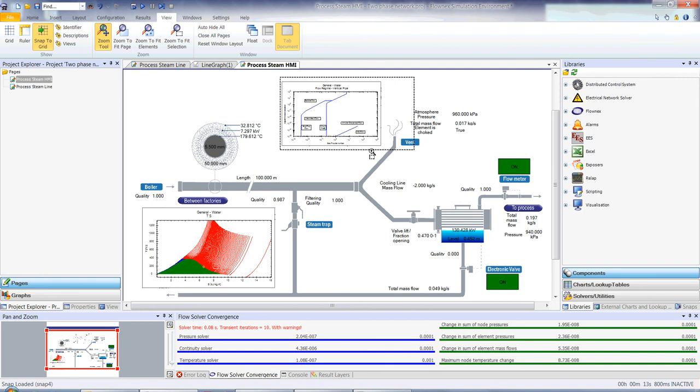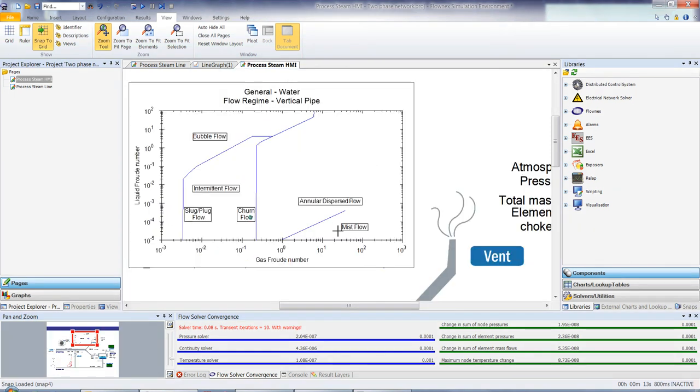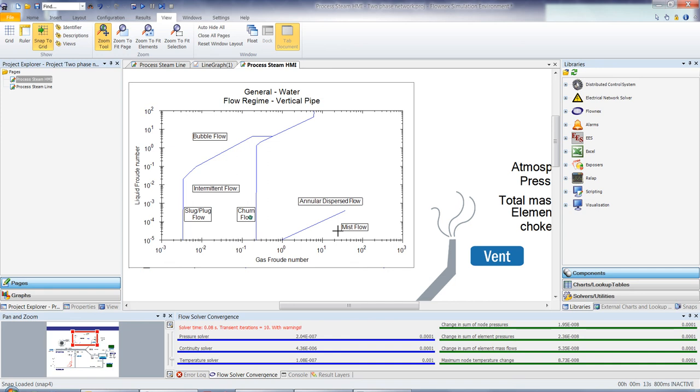If we have a look at the flow regime within the vertical venting pipe, we can see in this case we're in around the churn flow region. Now, this is directly linked to the heat transfer correlations that Flownex will use. So dependent on which regime you're in, Flownex will use the adequate heat transfer correlation. It will also then give you an indication of where you are. So if you are in an acceptable range, you have the ability then to change your properties and track how you'll be moving in and out of these specific flow regimes within Flownex.